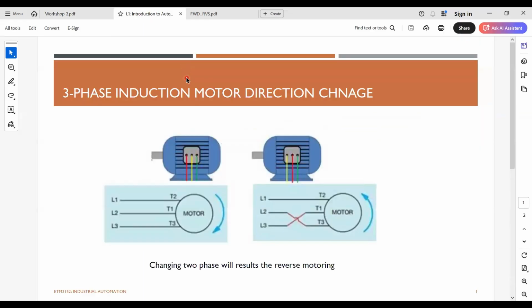Before we start the workshop, I would like to give you a recap of how a 3-phase induction motor direction is controlled. By looking at this diagram, you can see this is a 3-phase motor. We have 3-phase line into the motor, L1, L2, and L3. So assume this motor rotates in the clockwise direction. So if we want to rotate the motor in the anti-clockwise direction, or to reverse the direction, what you can do is change any 2 lines in the 3-phase supply that is fed to the motor.